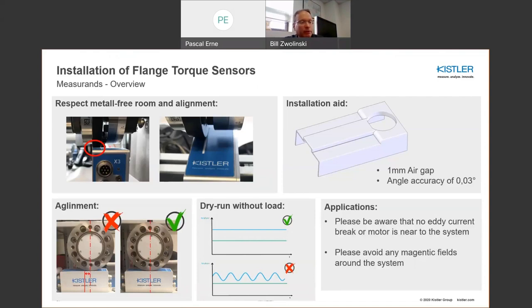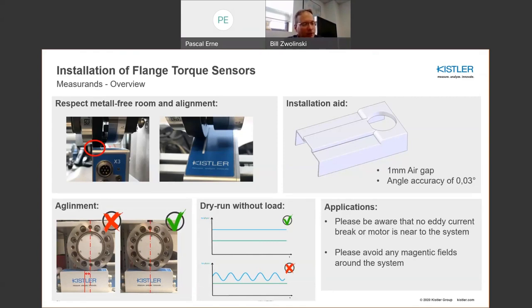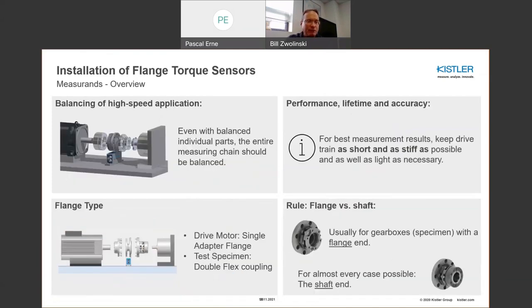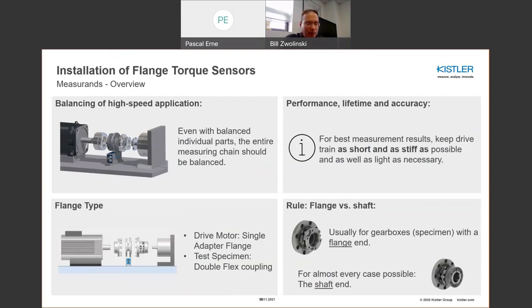A critical aspect of flange torque sensors is alignment — the rotor must be centered to the stator with about one millimeter separation. Tools are available nowadays to help make that alignment. If you're misaligned and do a dry run, you'll see a sine wave in the output, which is a fairly good indicator that you're off-center. With flange torque sensor installation, you use a single double flex coupling. Generally, flange types are used for gearbox applications, and almost every other case is the shaft type torque meter.